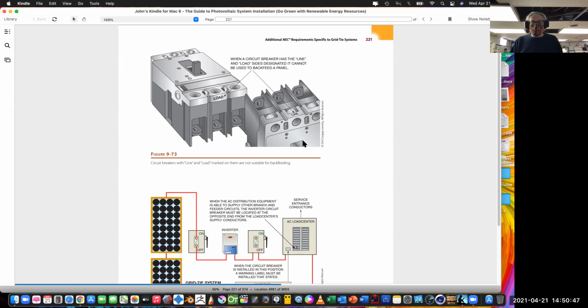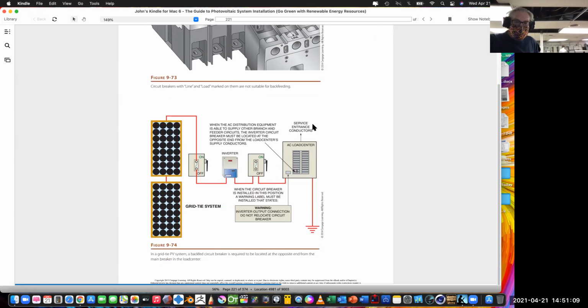Doesn't really matter. Generally I just try to bring every power source on the top side of the breaker, that's the line side. Anything that's a power source, put it on the top. Anything that it would power, put on the bottom, line load. That should be the way you do everything when you do electrical work, so people don't get confused looking at it like, why does that look backwards? Because it is backwards.